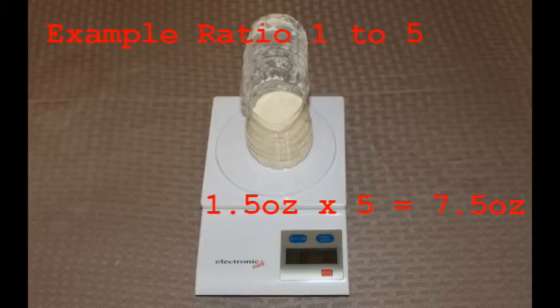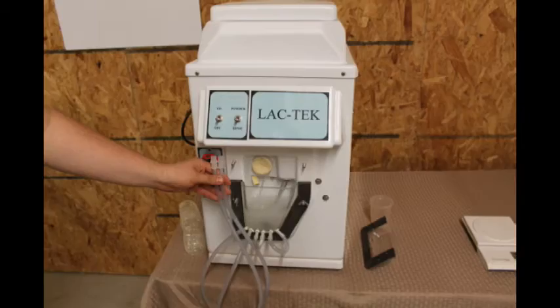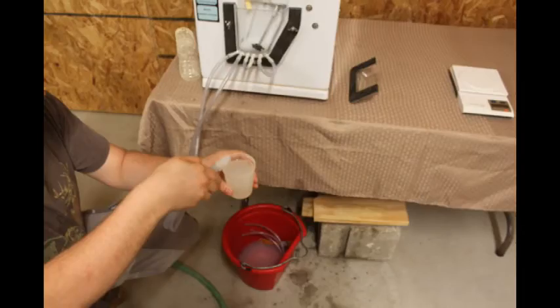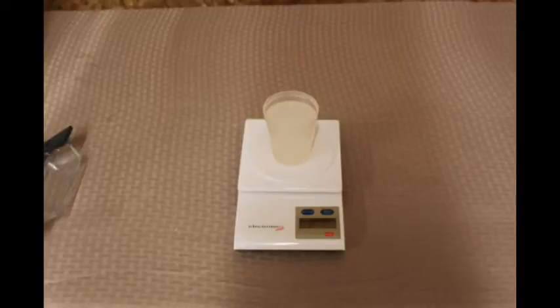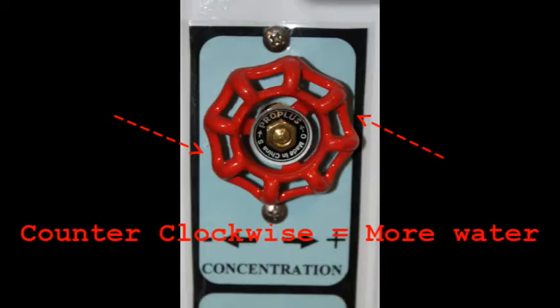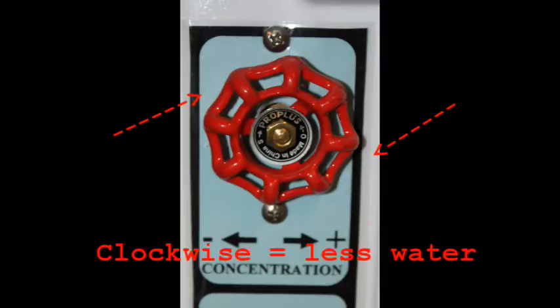Here we have 1.5 ounces. Take that times 5 for a 1:5 ratio and figure out that you need 7.5 ounces of water. Next, drain the water down to the tip of the sensor probe and stop draining when the bowl starts to fill again. Once the bowl is full of water, drain the water into a cup until the mixing bowl starts to fill again, then stop. Measure the water to figure out if more or less is needed to make the correct concentration. If additional water is needed in the calibration, twist the concentration knob counterclockwise. If less water is needed for the concentration, turn the water concentration valve clockwise.